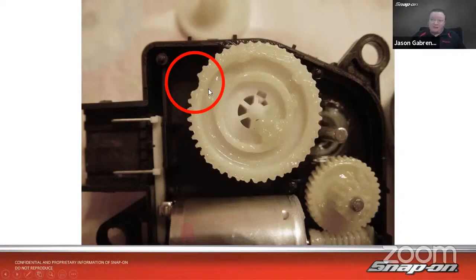That's probably the most common problem you'll see, and it can happen if the linkage gets messed up, or if a squirrel or chipmunk makes a nest in there. I've seen that happen before, with blower motors too, rodents like to make nests in there for some reason. You turn it on and it's making noise, you pull it down and it's full of nests. I'm sure you've seen that before too.